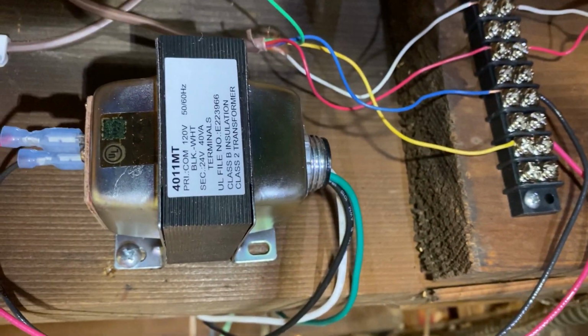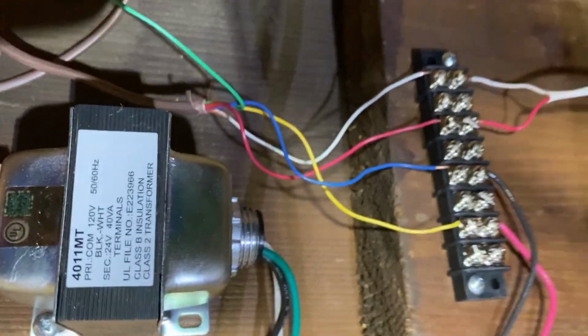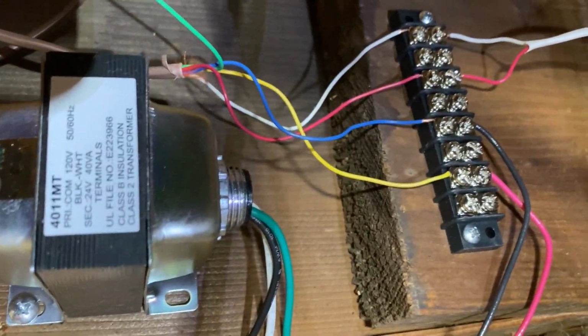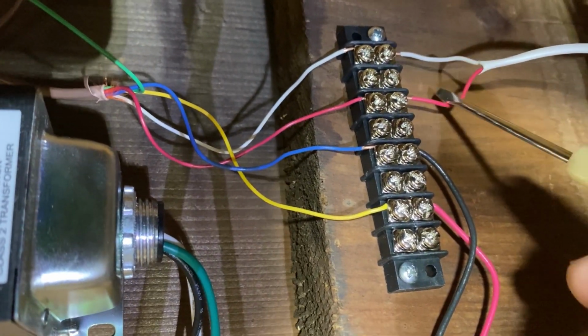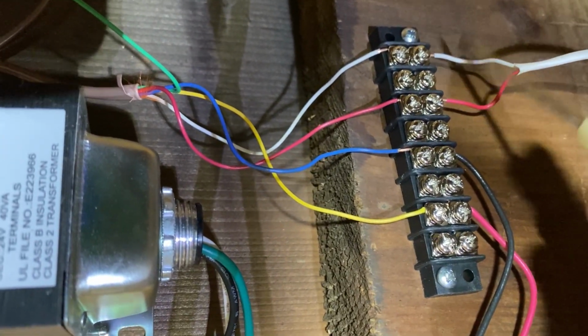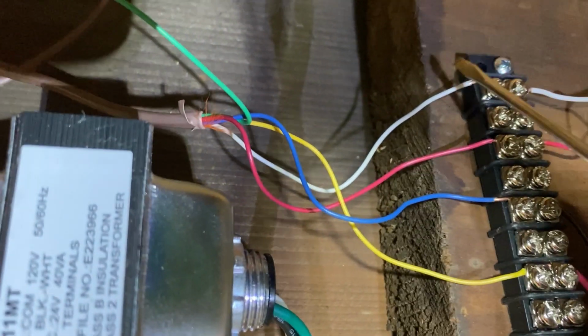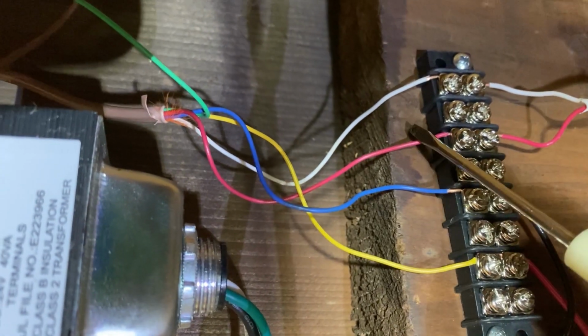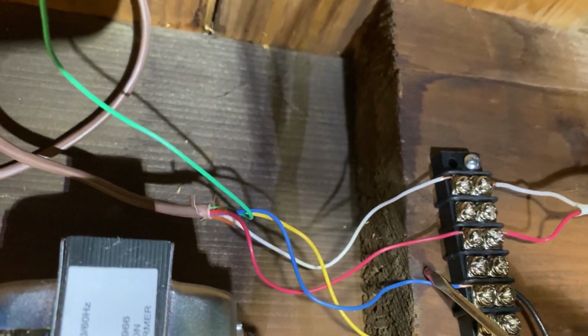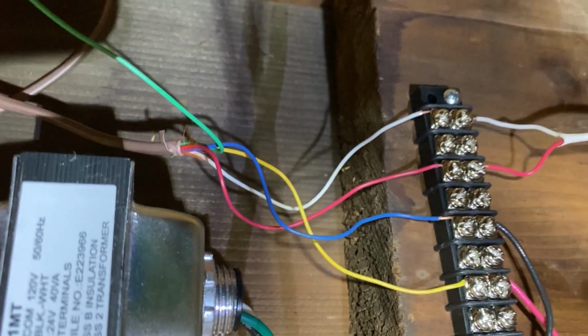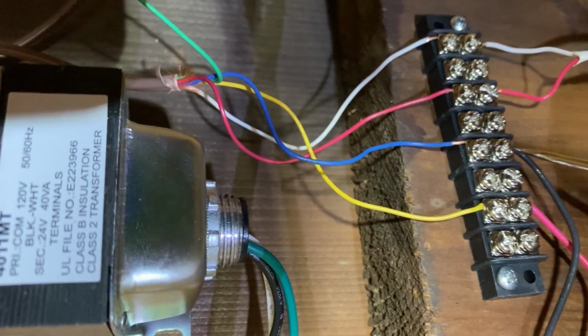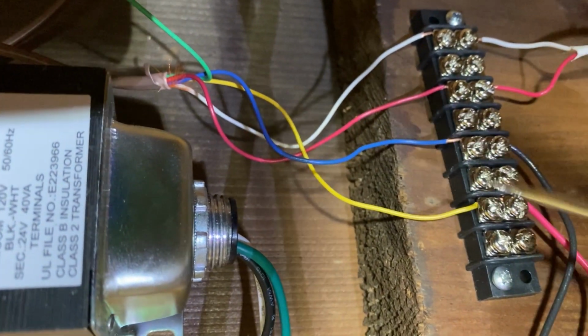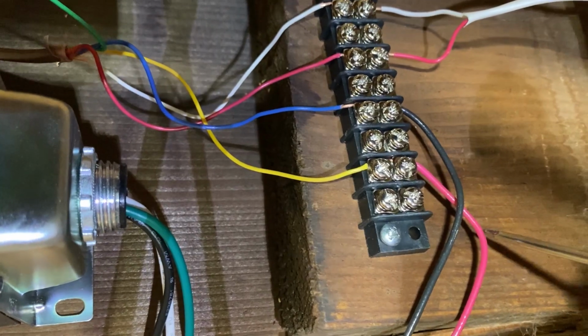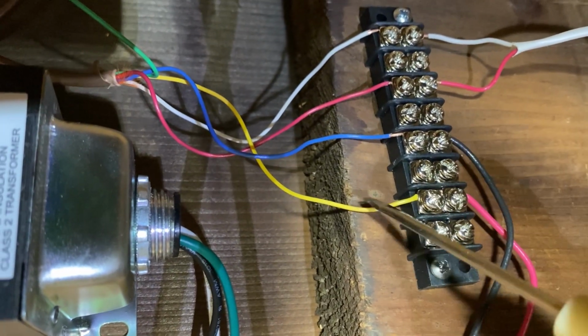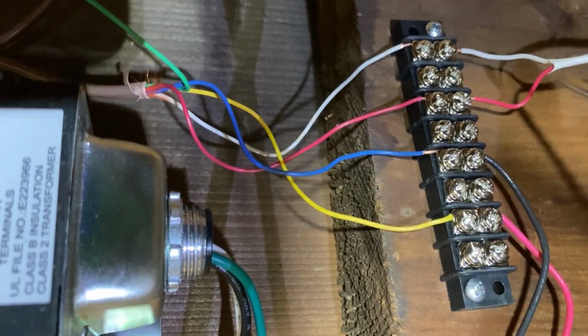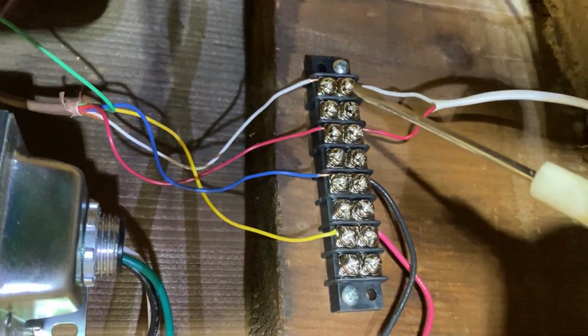So this is the type of transformer that you have to buy. It just feeds into 110, or feeds from 110. These are the two wires coming from the furnace. This is a 24 volt feed, and this is the return. This is the white wire, red wire, what I'm going to use as the common wire. So this is the C from the transformer, this black wire here, which becomes the C upstairs in the thermostat. This red wire here is going to be the R, which is going to be the RC up in the thermostat. So I use this block here, it's very convenient.